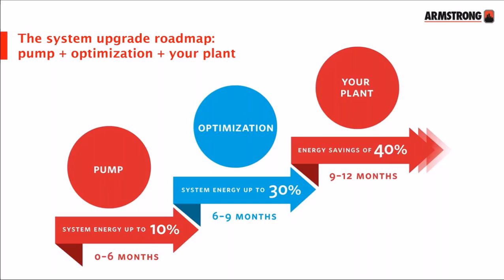So once we've surveyed the pumps and we've replaced the pumps and we start to see a financial saving and a carbon saving, we're remote monitoring that pump, so we can also harvest the data from the system through the pump, so we're learning whilst we're saving, and then that can inform us of optimization opportunities. Now that may be Armstrong controls being added to the system. It could be converting the system from a 3-pipe to a 2-pipe system, and all manner of other types of optimization. And within that phase, that second phase, you can look to save an additional 30% of energy.